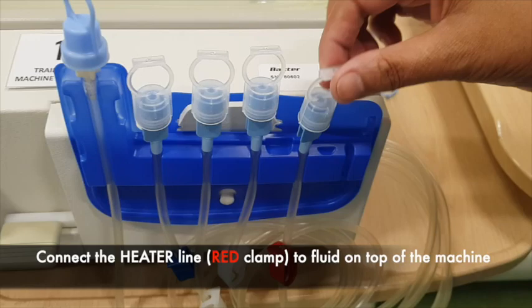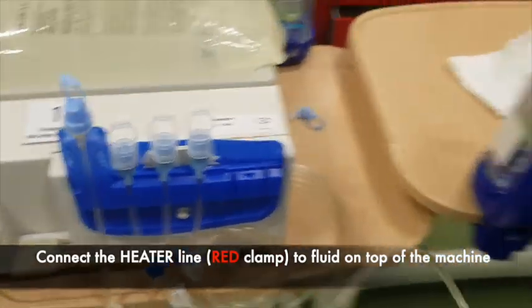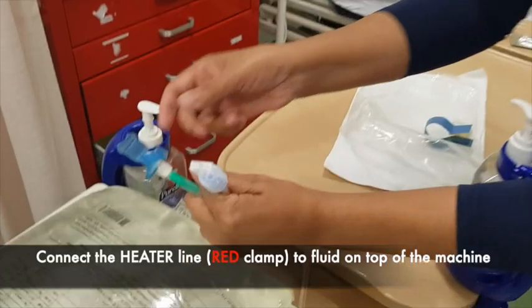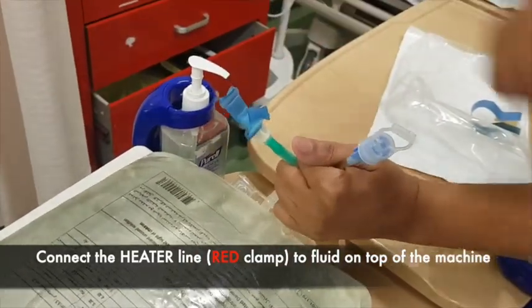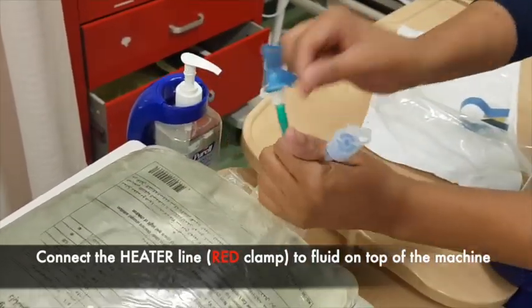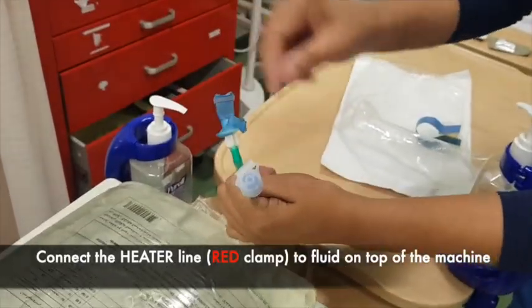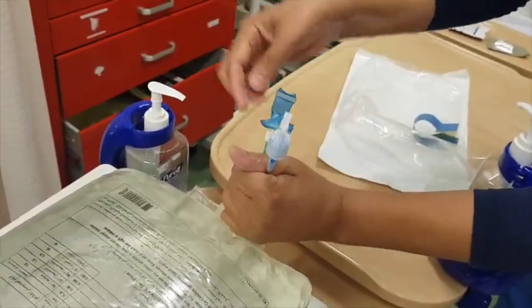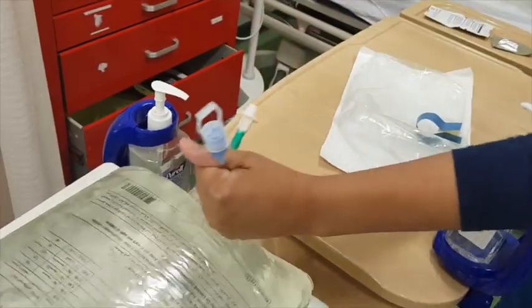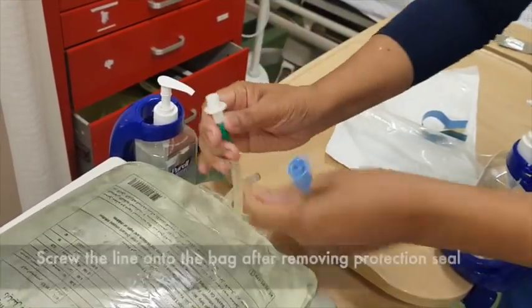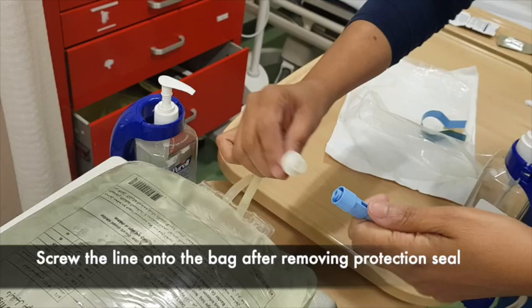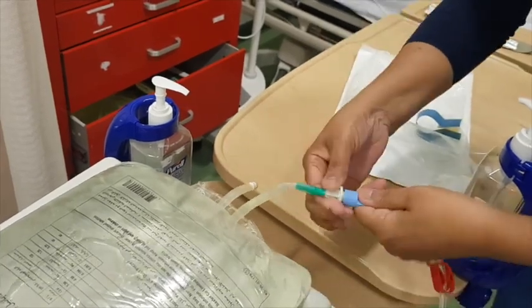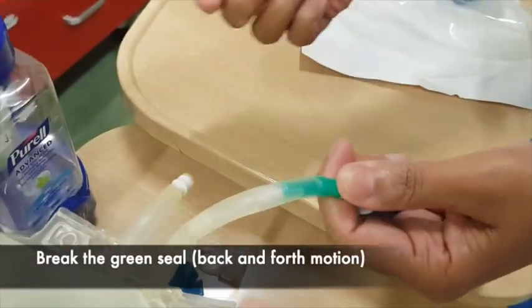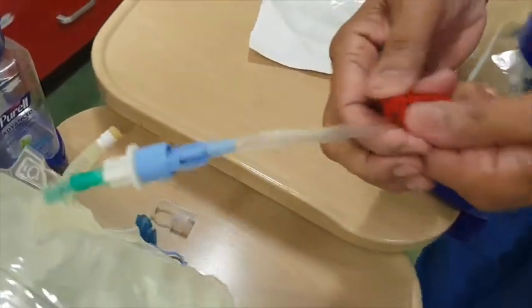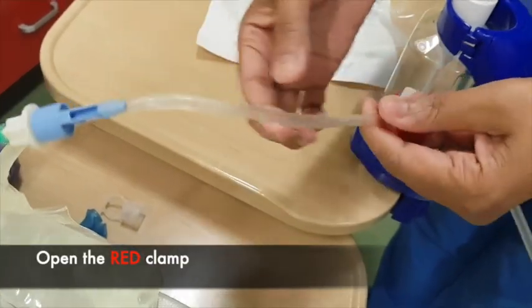Next, take the heater line, the one with the red clamp, and connect it on the fluid on top of the machine. Again, maintain aseptic non-touch technique when connecting the 2 lines. Break the safety seal and screw the line on the bag. Make sure that it is tightly connected. Break the green seal by using back and forth motion and open the red clamp.